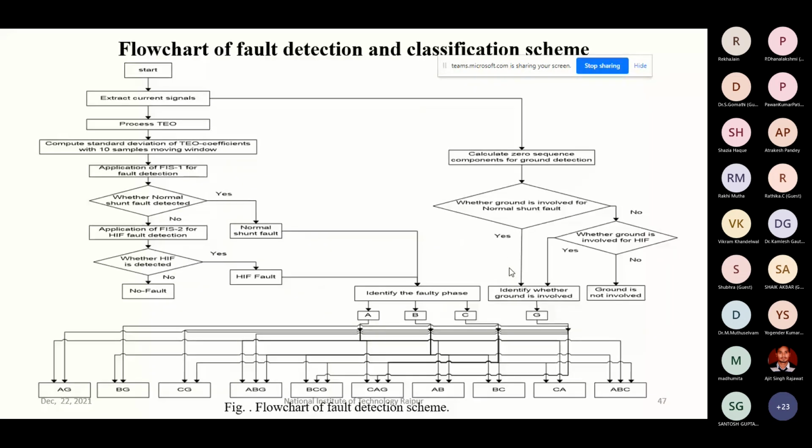A high impedance fault may occur in the system whenever the distribution line conductors fall onto a high impedance fault path, either through a tree branch touching the conductor or the feeder falling onto a faulty path which is of high impedance in nature, like roads with asphalt or damar road. This gives the nature of a high impedance fault, wherein the current magnitude is comparable to the nominal load currents and it cannot be identified by the conventional overcurrent protection scheme employed for the distribution lines.